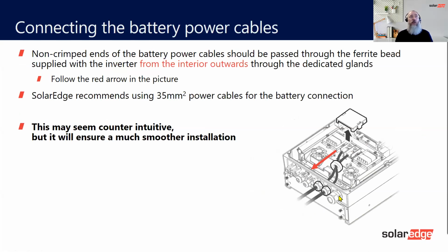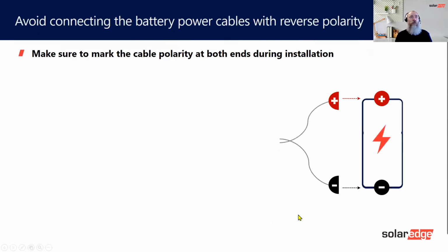Again, we spoke about this, about using 35mm cable and putting the lugs on the cable, putting the heat shrink on the cable, putting the ferrite bead on the cable, and then passing the cables through the inverter. That is the easiest way to do it. So from the inside out, that's the easiest way to do it. And don't forget, it's positive to positive and negative to negative. So when you make your cable, when you cut your cable and you put your lugs on it, make sure you mark up the positive cable at both ends, the same color.